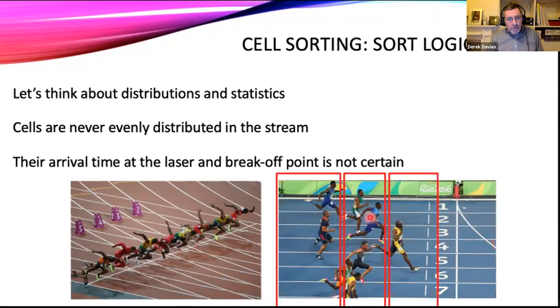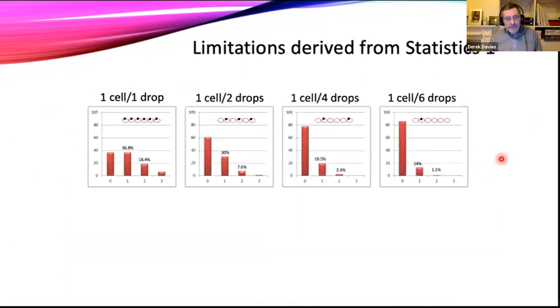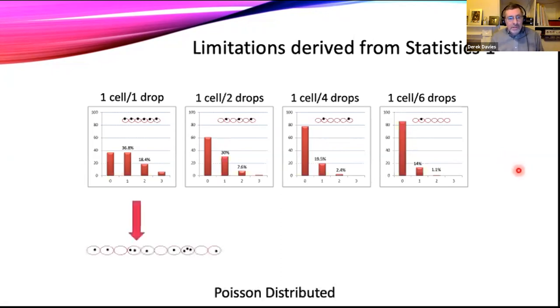We also need to think about the maths of cell sorting. You might think that if you're running cells at 10,000 cells per second you'd get one cell every drop — but life isn't like that. Cells are never evenly distributed in the stream: sometimes one cell, then very quickly another, then a big gap, then maybe three cells very closely together. Occasionally a drop has one cell, sometimes two or three. We're governed by Poisson statistics: if we're making drops at 60,000 per second, about a third of drops would have no cells, about a third would have one cell, and about a third would have more than one cell — and that last situation is what we want to avoid.